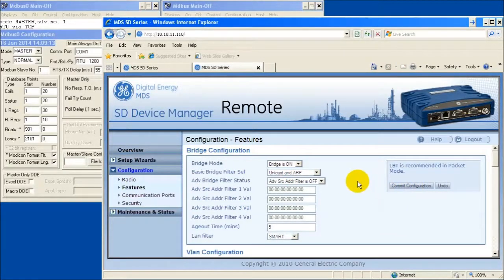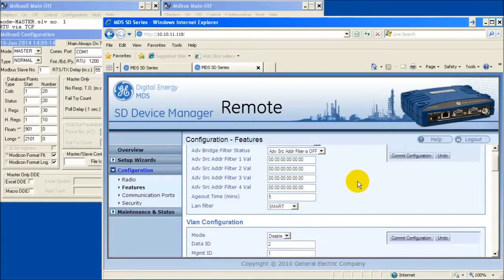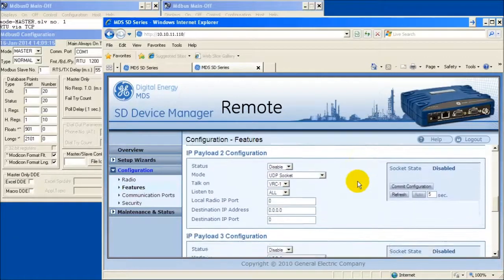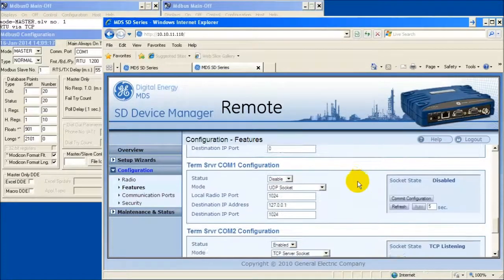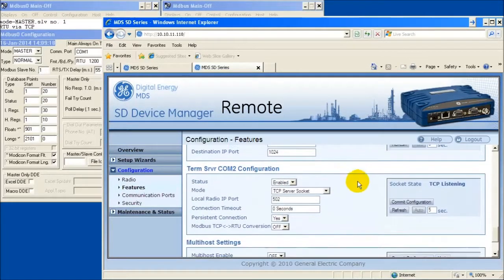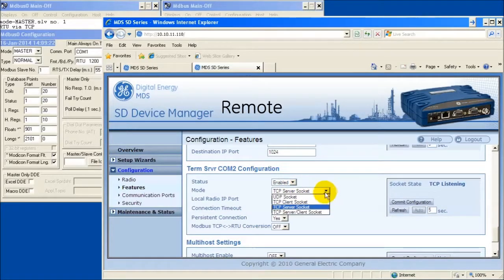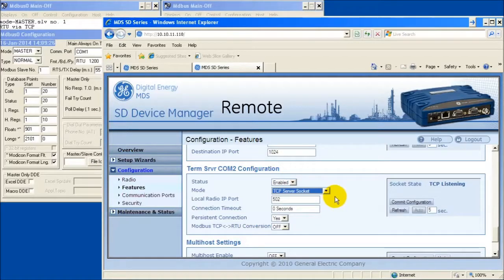Continue scrolling down to the terminal server COM2 configuration window. Select the proper mode. In this example, I will be sending RTU data via TCP to the remote and receiving a serial response on COM2. To do this, I will choose a mode of TCP server socket.